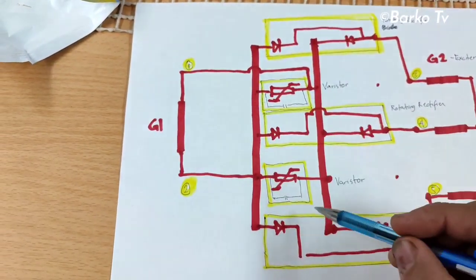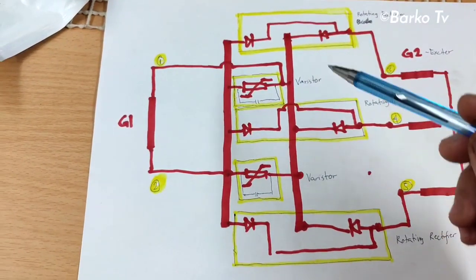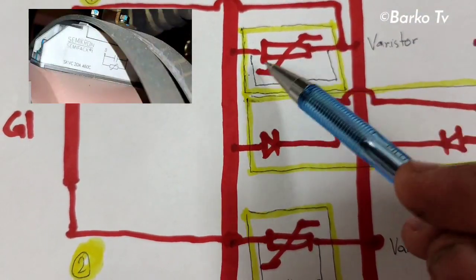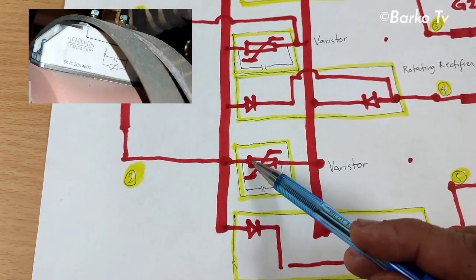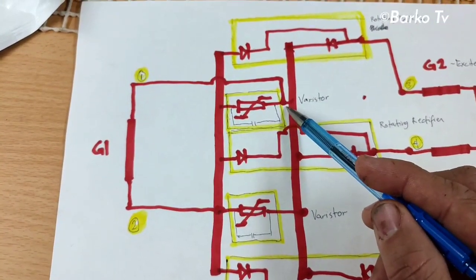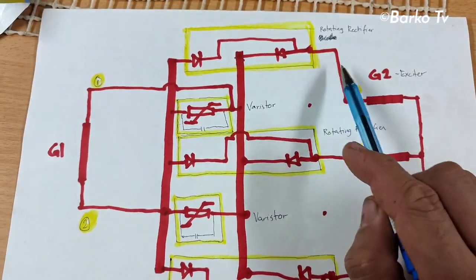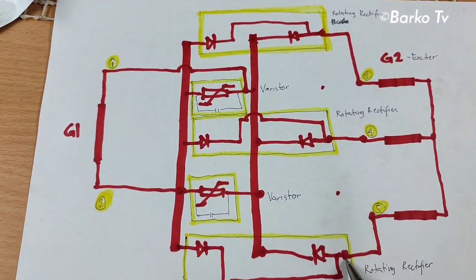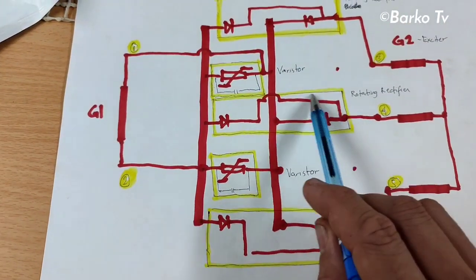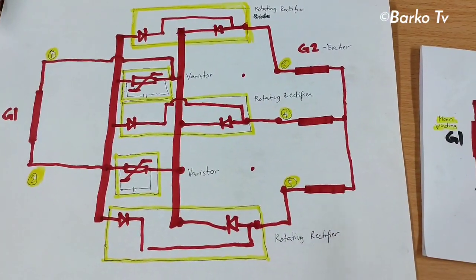G2 is the exciter, G1 is the main rotor winding. This is the varistor — the terminal is going to G1 and the other terminal is also going to G1. That is the first varistor. Number two varistor: in actual there are two varistors but in the schematic only one. All connections are the same. The end of the first rotating rectifier goes to the exciter, the second to the next exciter, and the third to the next — this is the complete set of rotating rectifiers.